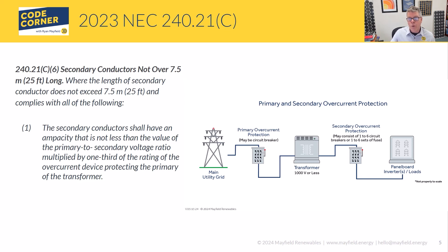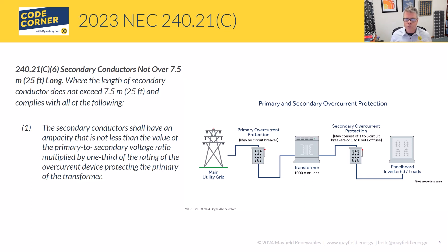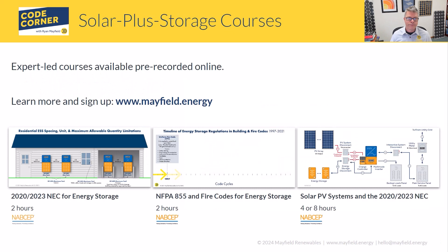Sub-part two of C6 talks about secondary conductors terminating on a single circuit breaker or set of fuses, and also that those secondary conductors are protected from physical damage. That rounds out those rules. Parts C1 through C5 are specific to different applications, so if you meet those requirements, look at and apply those rules for your transformers.